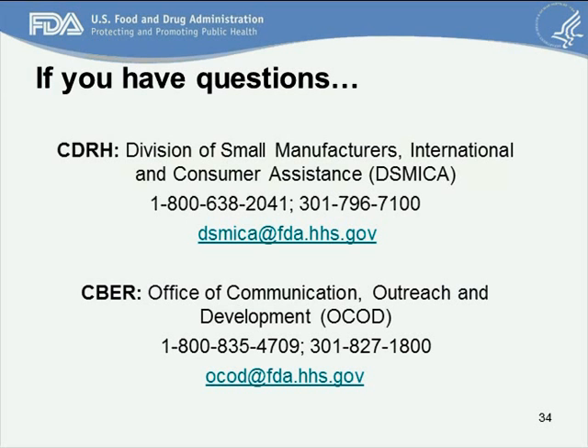And so there are currently no new pre-IDEs anymore. There are no files that are given assignment numbers that begin with the letter I. Any type of pre-submission, whether it's for an IDE or a PMA or an HDE or anything, it's given a Q number.